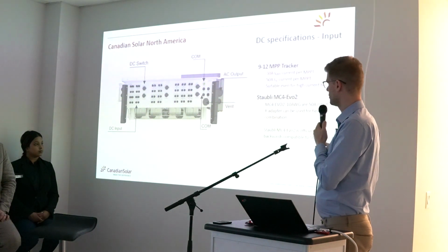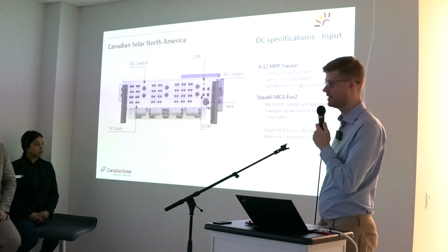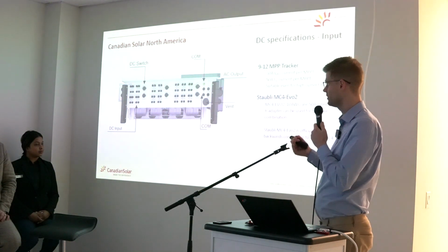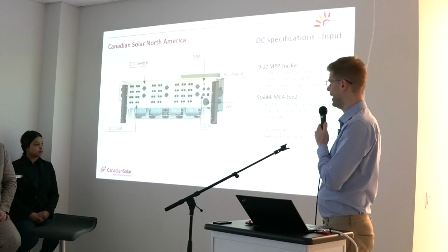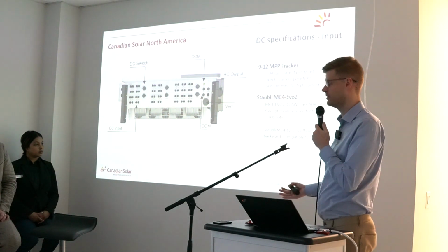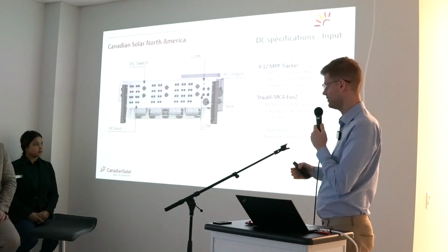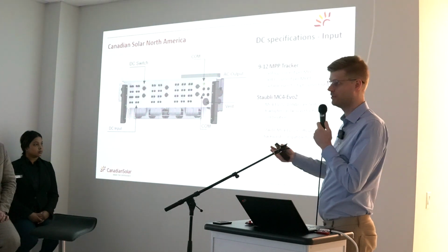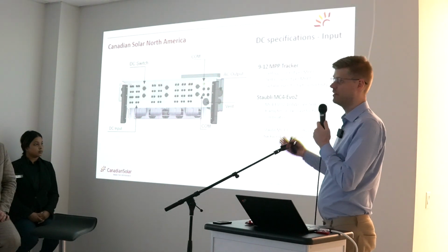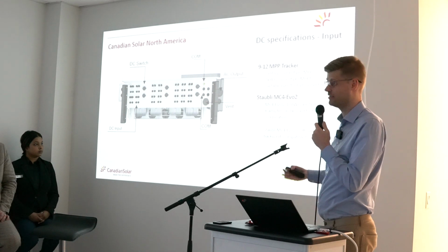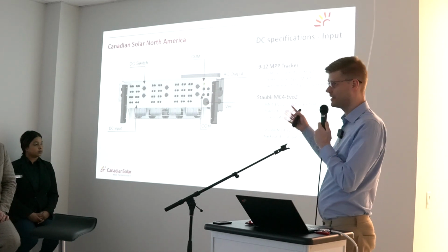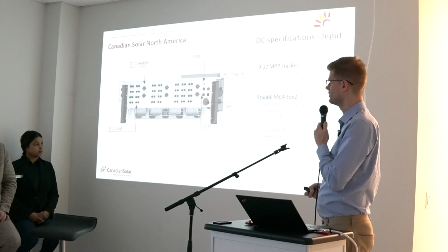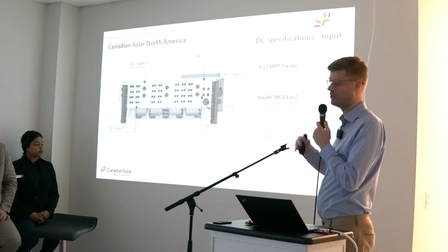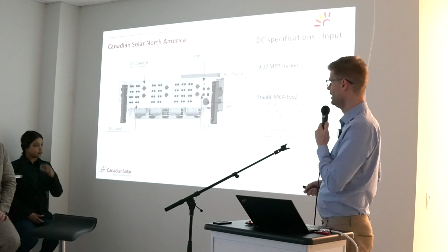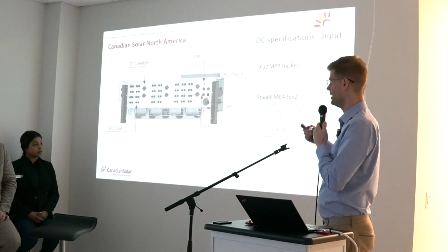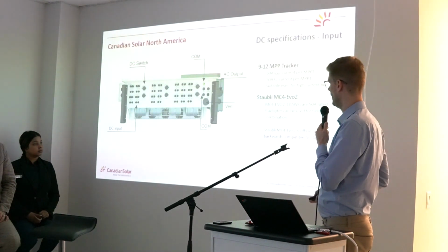Stäubli MC4 connector. So Stäubli is the former multi-contact company. These are the original MC4 and the brand name. And with the requirements by Code in Canada, you have to have matching connectors. In this case, your module or your home run to the inverter already has probably an MC4 because that's the standard super available. And you can directly land those MC4s on the bottom of the inverter without any whips or adjustments or searching for the specific brand connector if it would not be genuine MC4.